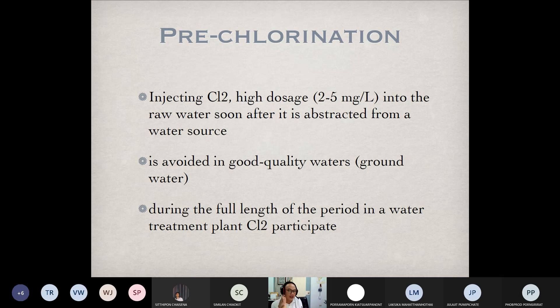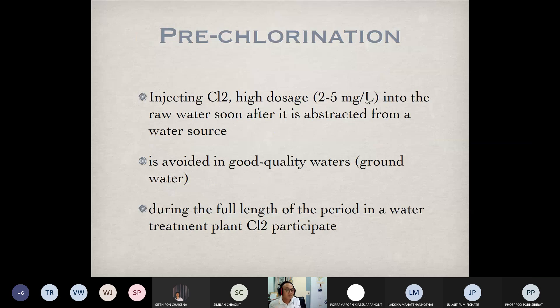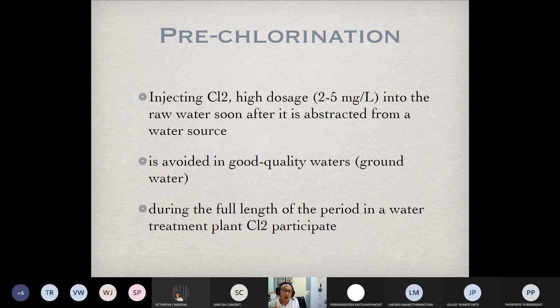We keep the chlorine at a high dosage — enough to oxidize reducing agents, remove color and odor, prevent slime formation, and kill some algae. This amount is actually very similar to what we apply to swimming pools, where we need at least 5 ppm. But for normal tap water, the chlorine residual should be around 0.2 to a maximum of 2 mg/L only.